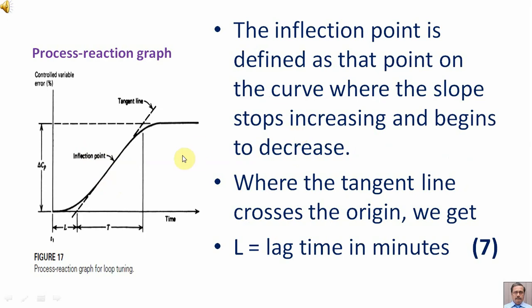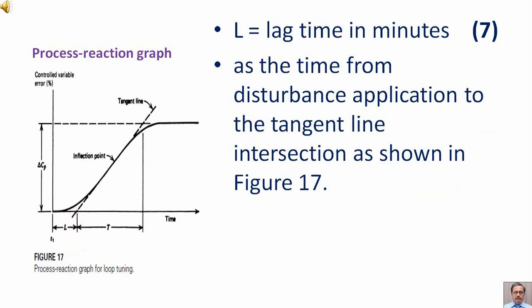The inflection point is defined as the point on the curve where the slope stops increasing and begins to decrease. Where the tangent line crosses the origin, we get L equal to lag time in minutes. Equation 7: L equal to lag time in minutes, as the time from disturbance application to the tangent line intersection, as shown in Figure 17.